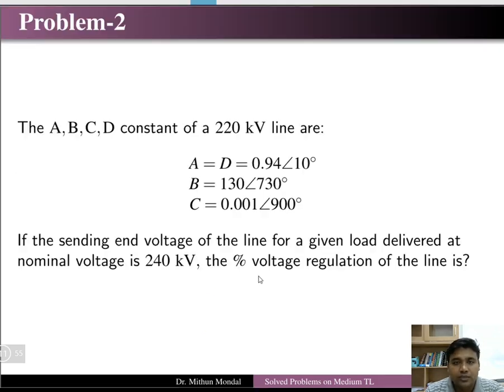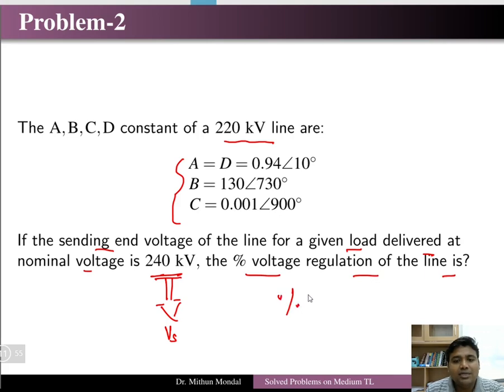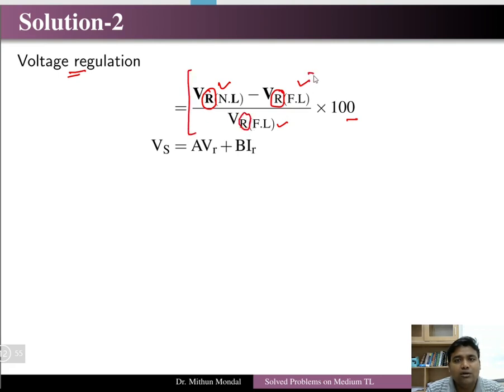Problem 2: Given the ABCD parameters of a 220 kV line, if the sending end voltage for a given load delivered at nominal voltage is 240 kV, find the percentage voltage regulation. The formula is: % VR = (V_no-load − V_full-load) / V_full-load × 100, referenced at the receiving end.